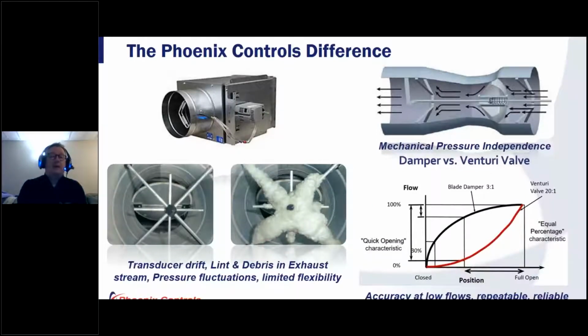Now, when I talk about Phoenix controls, many of you, like I said, are familiar with the Venturi valve, right? And that's the difference between what is typically used in a hospital today, which is the VAV box, versus the mechanical pressure independence of the Venturi valve. And not knocking the VAV box so much, it's just, I think for many of these spaces that we're seeing in healthcare, it may be a little bit misapplied, right? And so we have some data to share, to try to show you that. But let's talk a little bit about the differences.